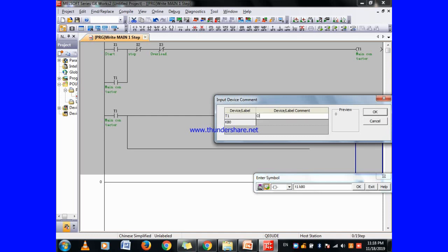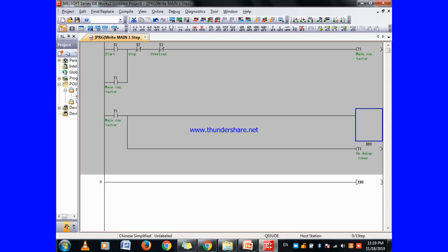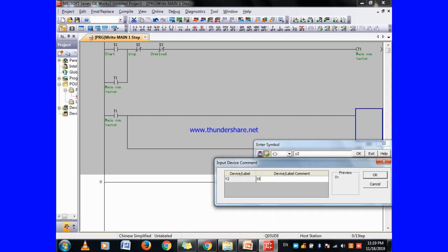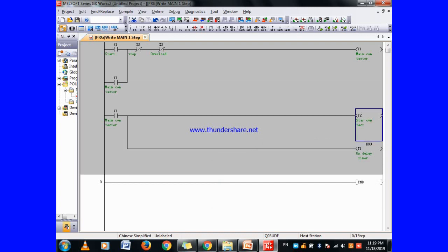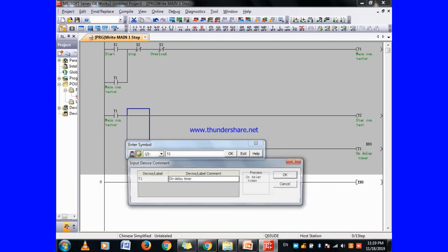This is an on-delay timer T1. We then take the star contactor output Y2. For the star contactor Y2 to turn on, in this condition the timer should not yet have elapsed, so we place a timer NC contact before Y2. This means while the timer is counting, the star contactor Y2 remains on.